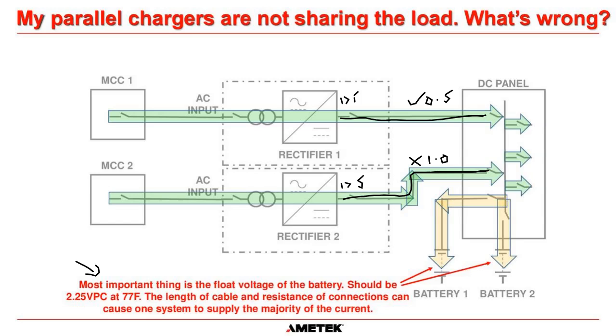That means at the DC bus, this charger is putting out 134.5 and this charger is putting out 134. And whoever has the highest voltage is going to win. It's as simple as that. So rectifier 1 or charger 1 is probably going to supply all of the current to your load circuits. Okay? So many people will say, okay, well, what we'll do is we'll adjust the top charger. Actually, we'll have to increase it to 135.5, and we will change this one to 136. And then we should have 135 volts there and 135 volts there.